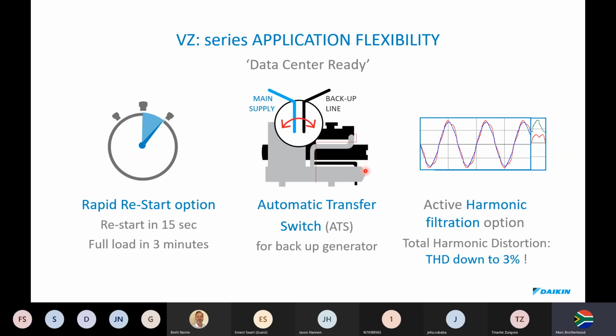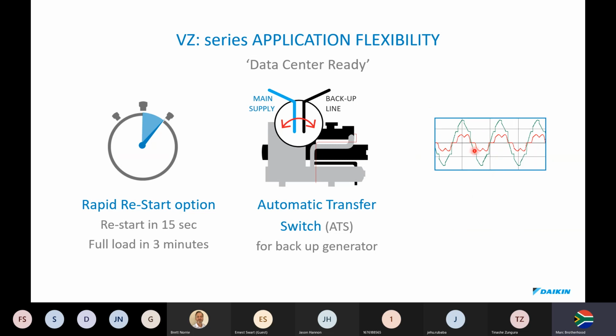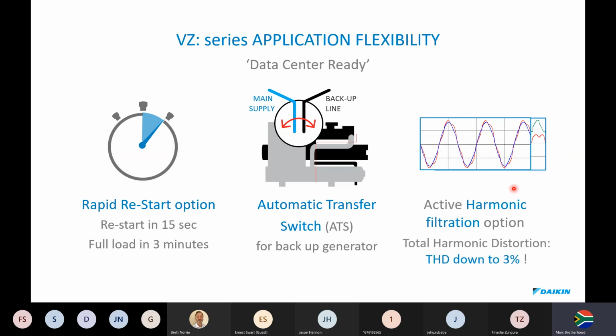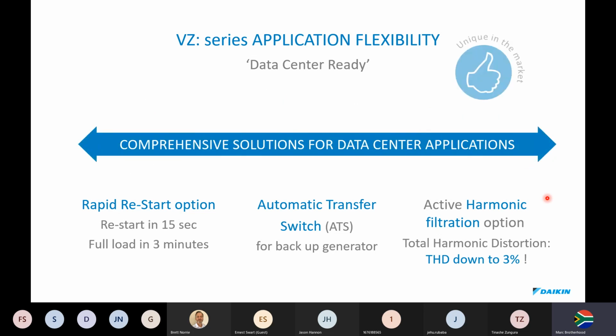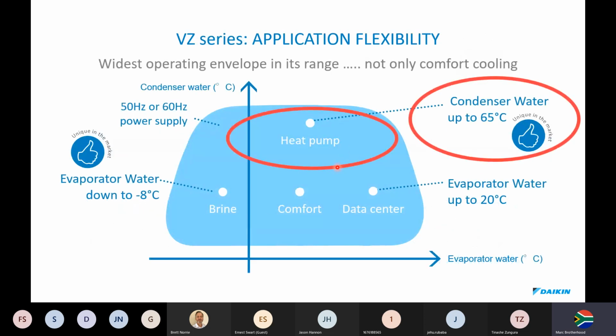So if you choose a chiller specifically, you have this as an option, active harmonic filtering, and we create a very pure sine wave. So we're not going to generate harmonics back like this and affect their power supplies and damage their computer equipment. So that's a big advantage that we offer, harmonic filtering on the inverter chiller. So we offer comprehensive solutions for data centers.